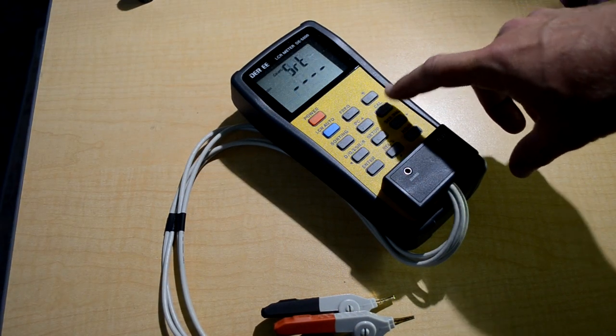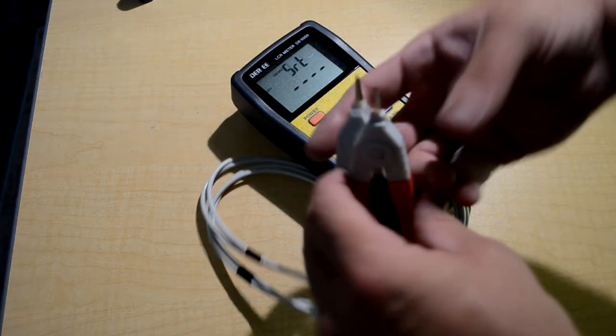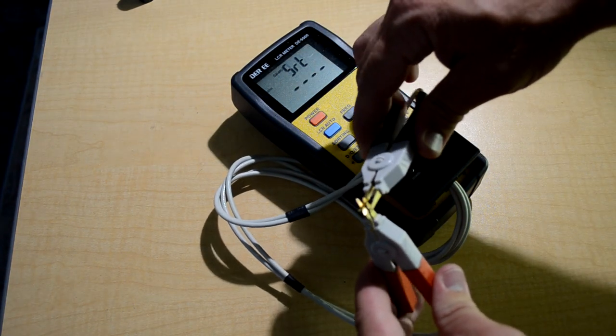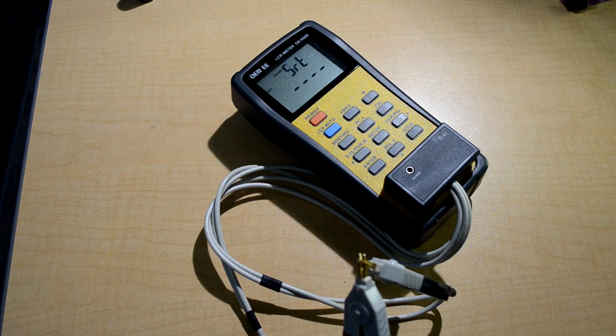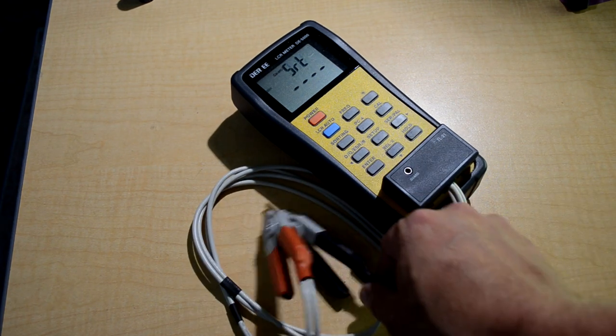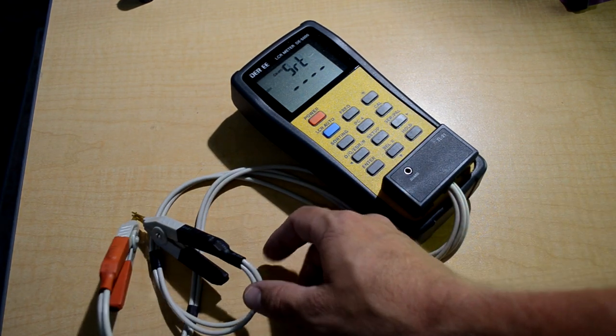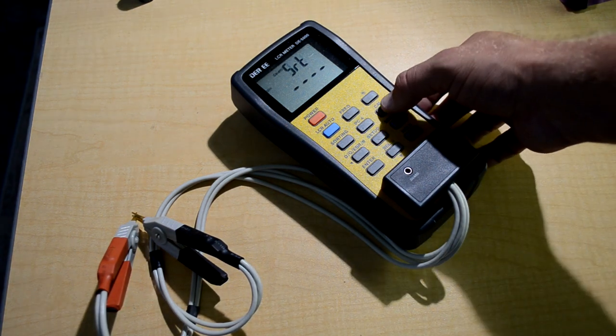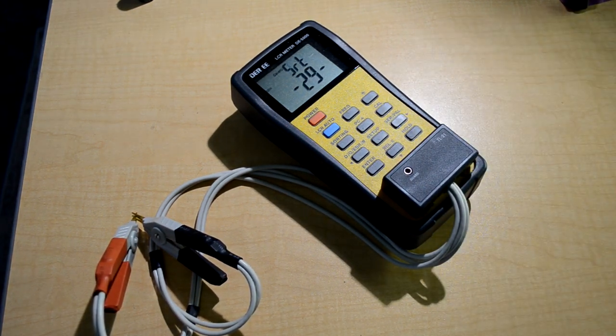And then you click the calibrate button again, and now you need to short it. So we'll clip the two ends together on there and then set it up to where we can see it as well as go back to the meter, press calibrate again, and we'll start another 30 second countdown.